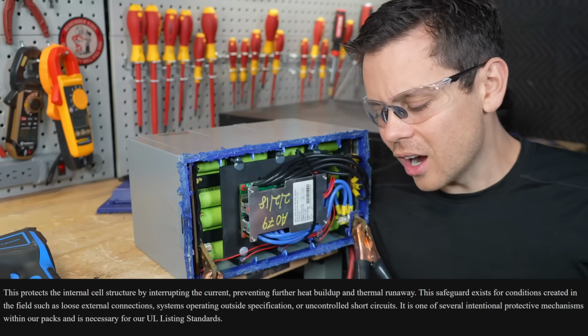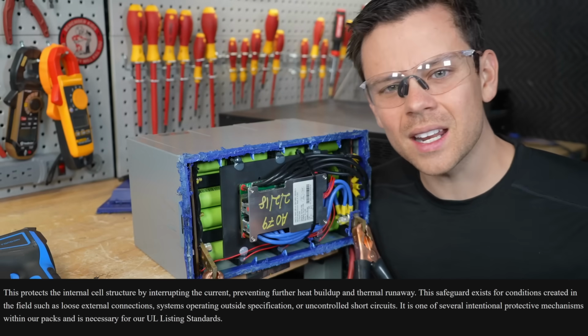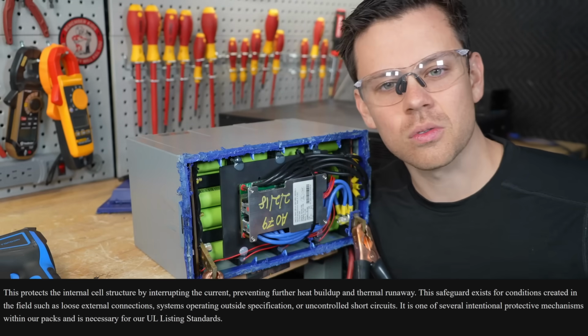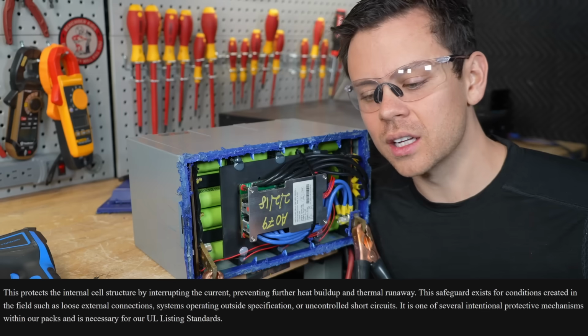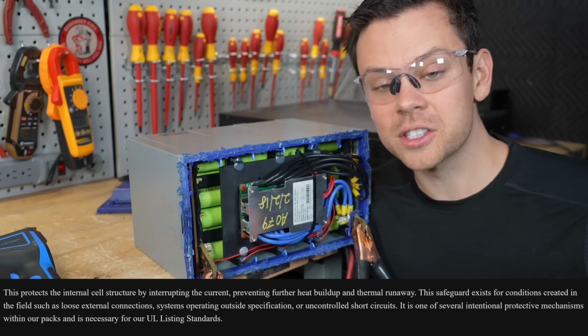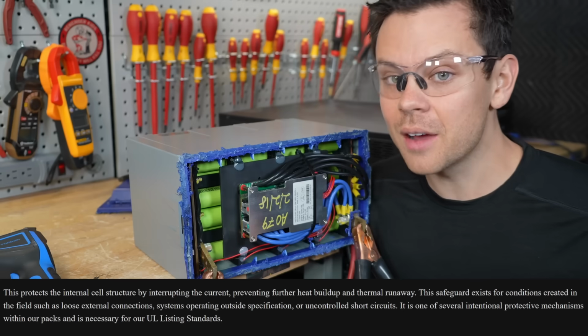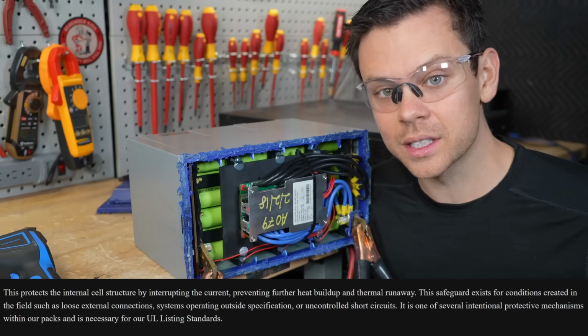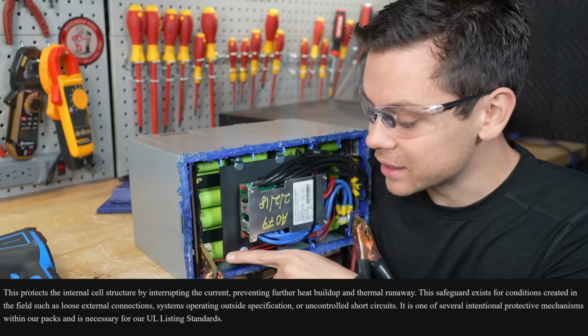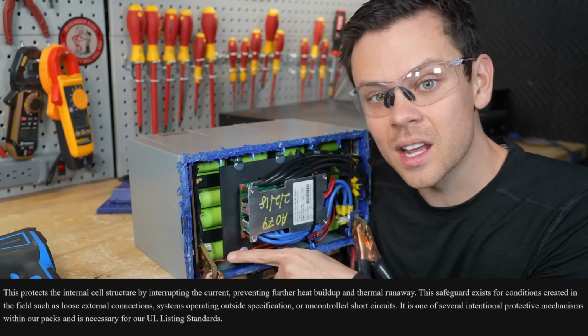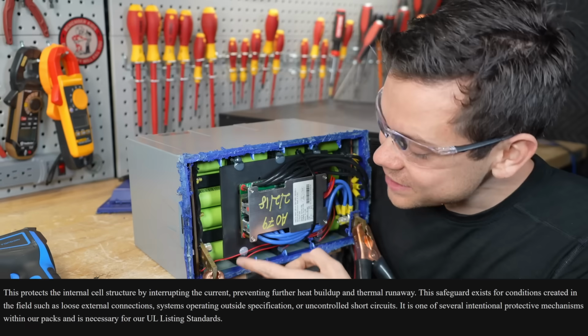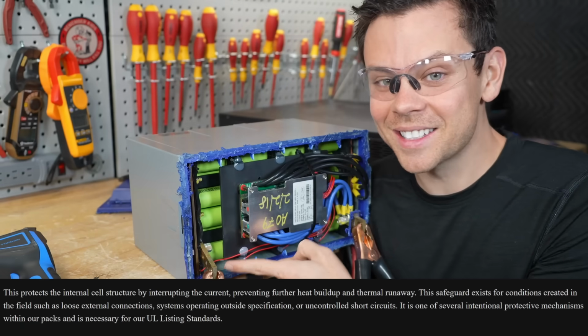And the final one is uncontrolled short circuits. What does that actually mean? Uncontrolled — if you have a short circuit, you need a protection device because you're not there to control it. You need a fuse or a circuit breaker that's UL listed. If a laboratory is passing this as an overcurrent protection device, they need to be investigated. This is not disconnecting. It is not.